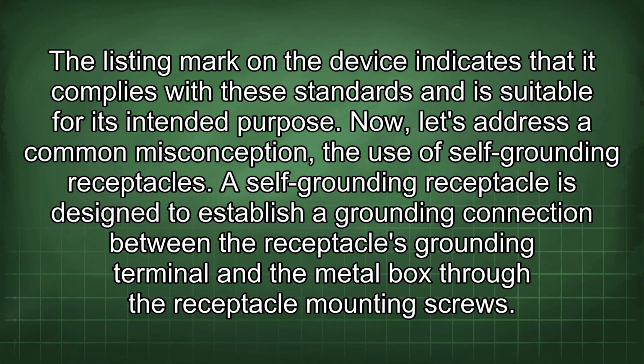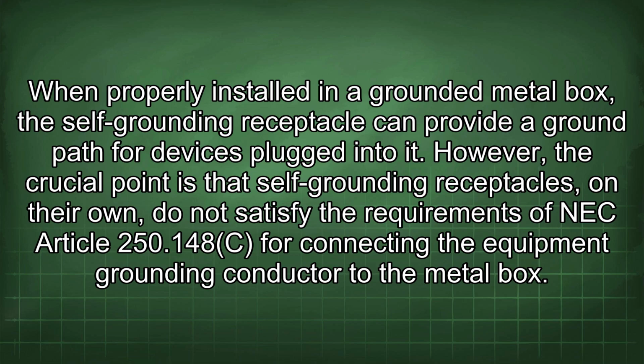Now let's address a common misconception: the use of self-grounding receptacles. A self-grounding receptacle is designed to establish a grounding connection between the receptacle's grounding terminal and the metal box through the receptacle mounting screws. When properly installed in a grounded metal box, the self-grounding receptacle can provide a ground path for devices plugged into it. However, the crucial point is that self-grounding receptacles, on their own, do not satisfy the requirements of NEC Article 250.148C for connecting the equipment grounding conductor to the metal box.